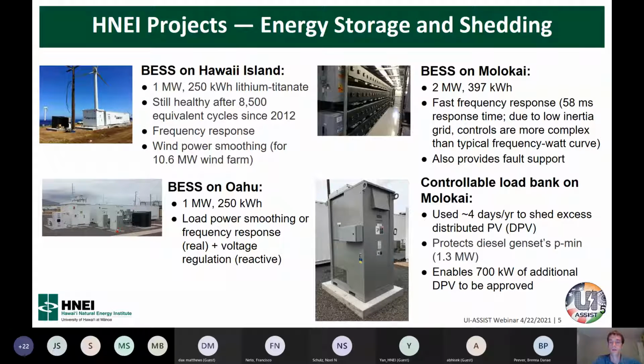Another unique aspect is this load bank that HNEI has installed and now turned control over to the utility. It's basically a resistive load bank that can be controlled fairly quickly to address situations where you have too much PV and you're pushing your diesel gensets below their minimal operating points, which would be an unstable point. It could also violate EPA regulations because those diesel gensets might pollute more at those levels.